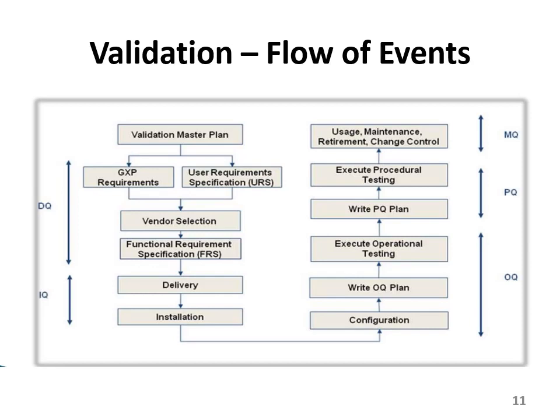Then you are going to go through two steps. The first step is the GXP requirement. This is actually good practice requirements. GXP is an abbreviation of good practice requirements, and the other side is the user requirement specification, what the user is requiring or needs to get from you, that is the user requirement specification, URS. So you have two different categories which you follow while designing your master plan for the validation: you have to see the requirement specifications of your user or your client, plus you need to keep good practices in your area of work.